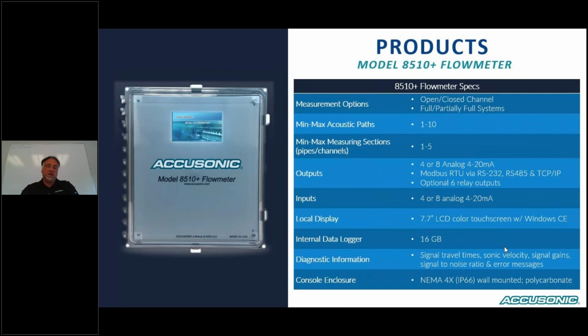Getting into the electronics console itself, our Model 8510 Plus, we basically sell two options. It's a 4-path or a 10-path unit. Each electronics console comes with the ability to measure up to 5 different pipes. And the number of pipes you can have depends on the number of paths you have assigned to each pipe. For the 4-path flow meter, we have 4 analog inputs and outputs that come standard. For the 10-path flow meter, we have 8 analog inputs and outputs that come standard with the flow meter.